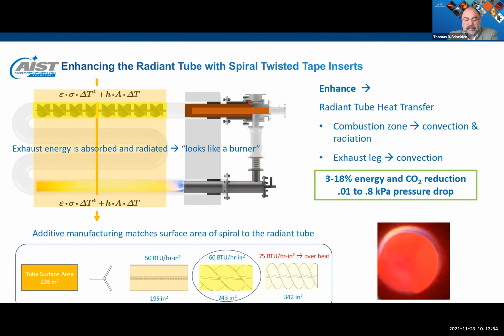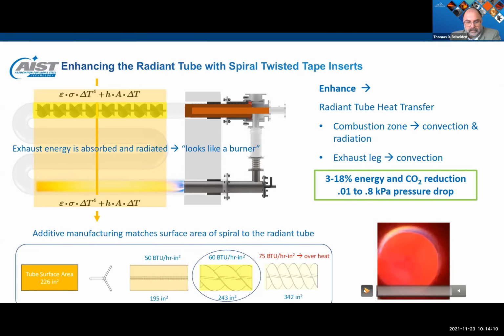While increasing the twist rate further enhances the heat transfer, overheating may occur. However, this may be an advantage in, for example, a radiant tube made of ceramic. Here's a quick visual demonstration of twisted tape inside a radiant tube. Let's move this over here. Typically, 3 to 18% energy and CO2 reductions occur with minimal pressure drop.